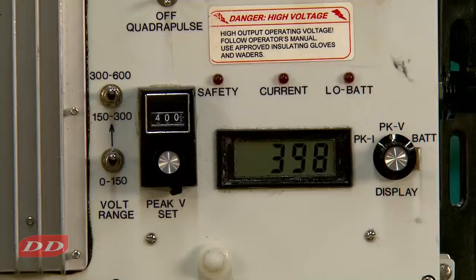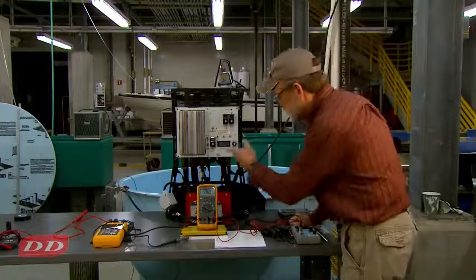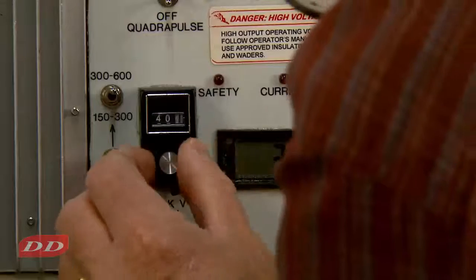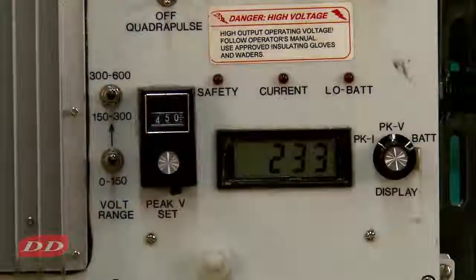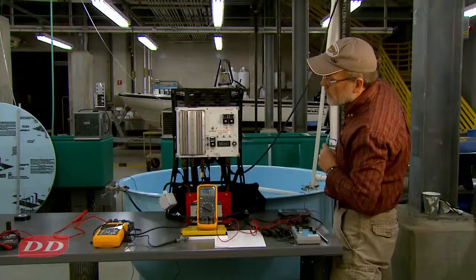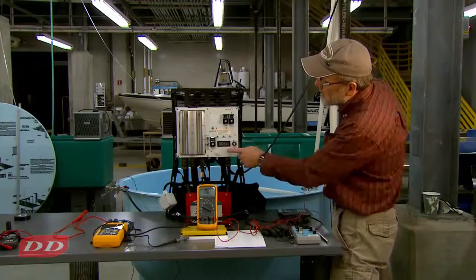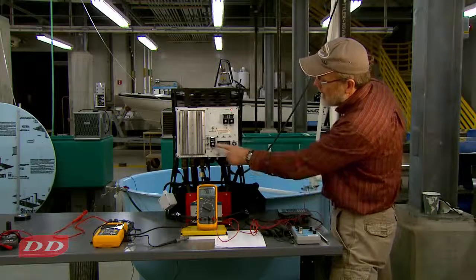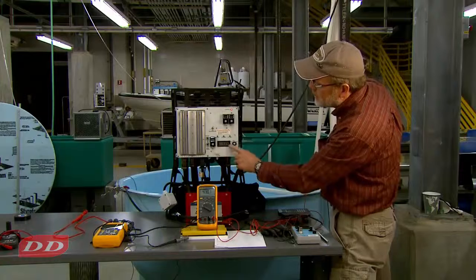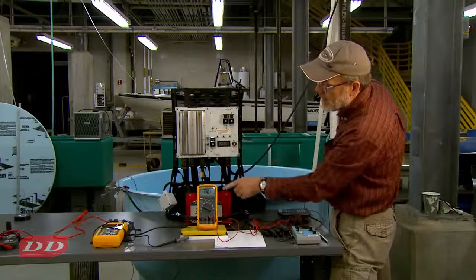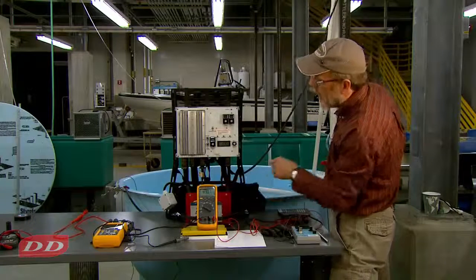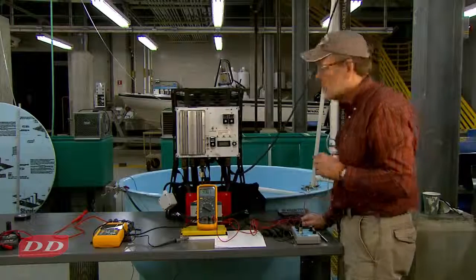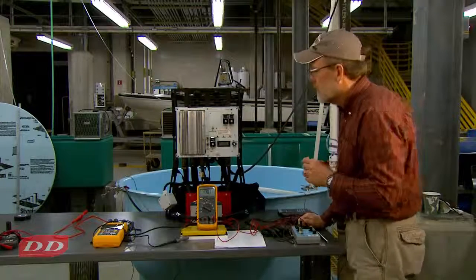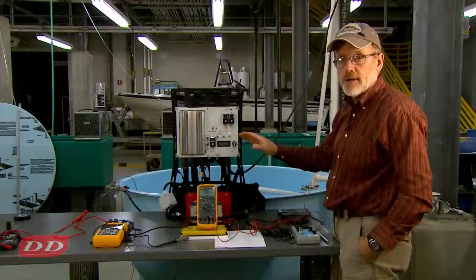398, 407. Good agreement. Now we're going to go to 450. And now we see we're not getting what we had dialed in. We dialed in 450. We're only getting 414. And then, she cut off, so we had an overload there. But you can see we're getting to the limitations of the machine.